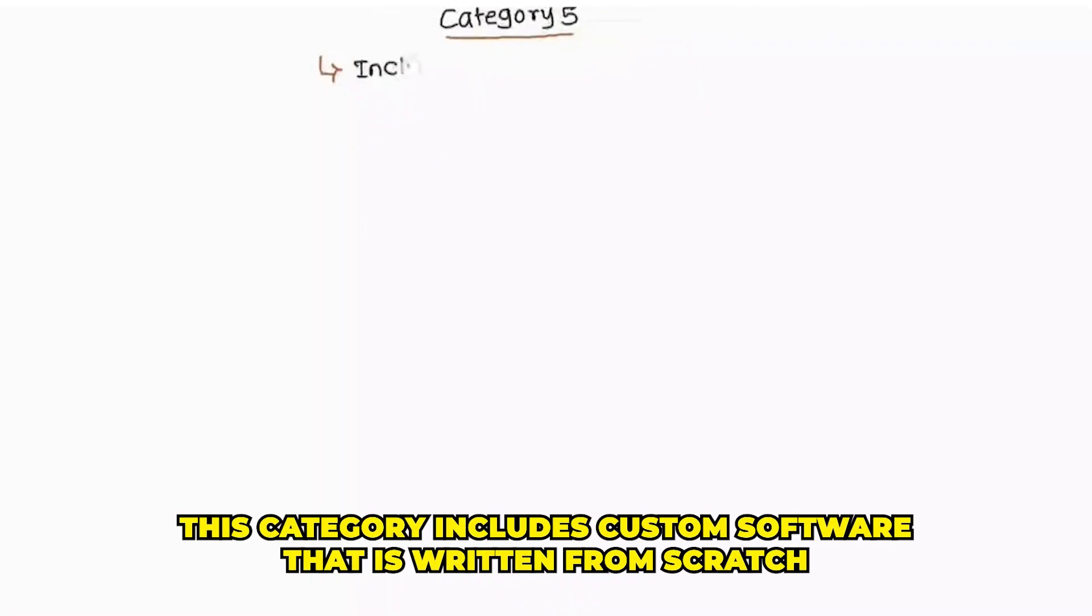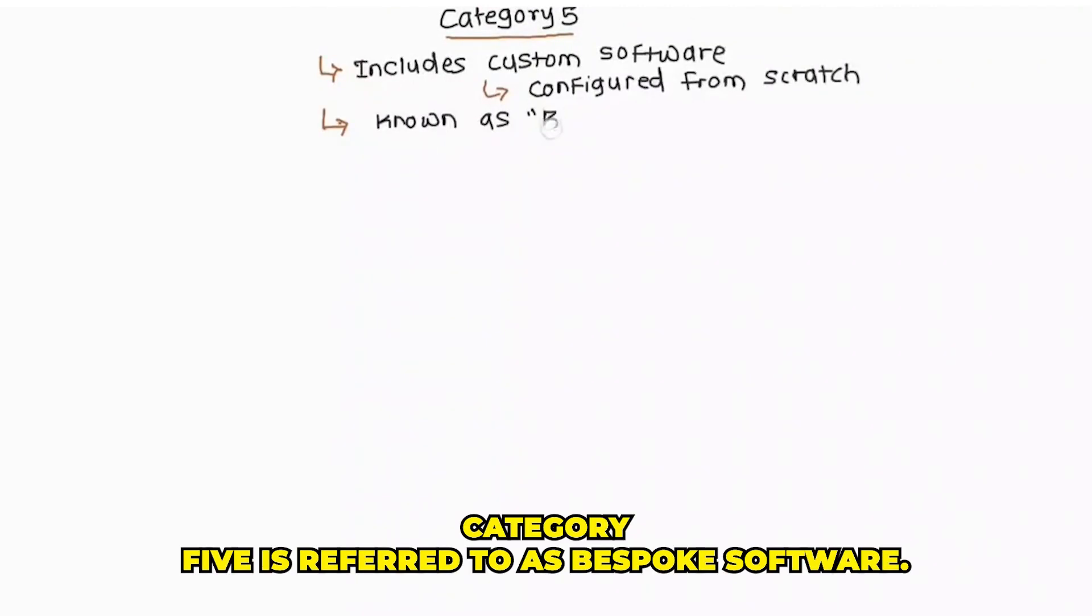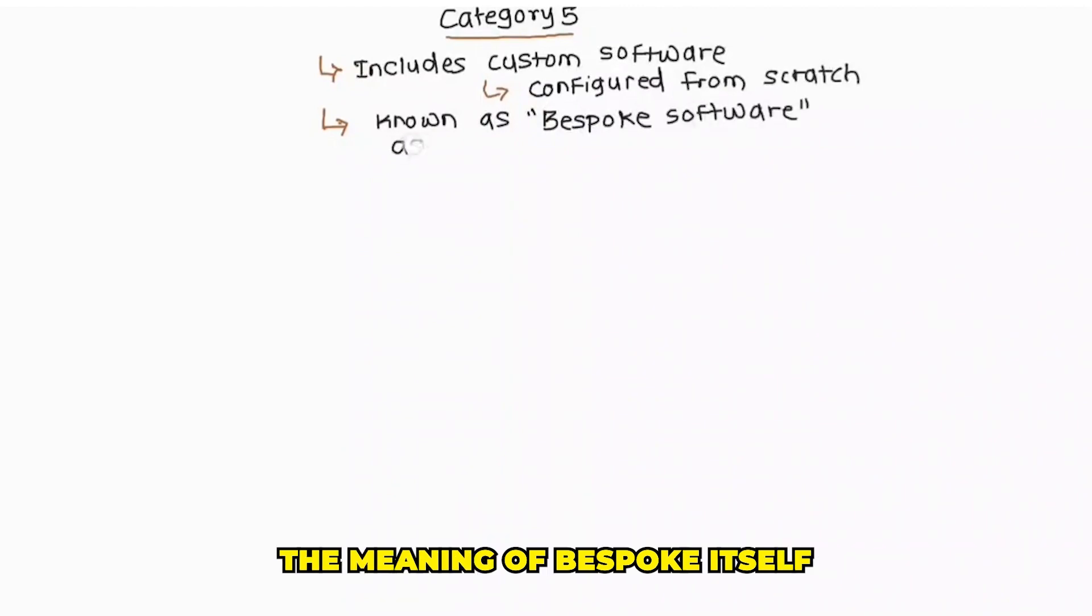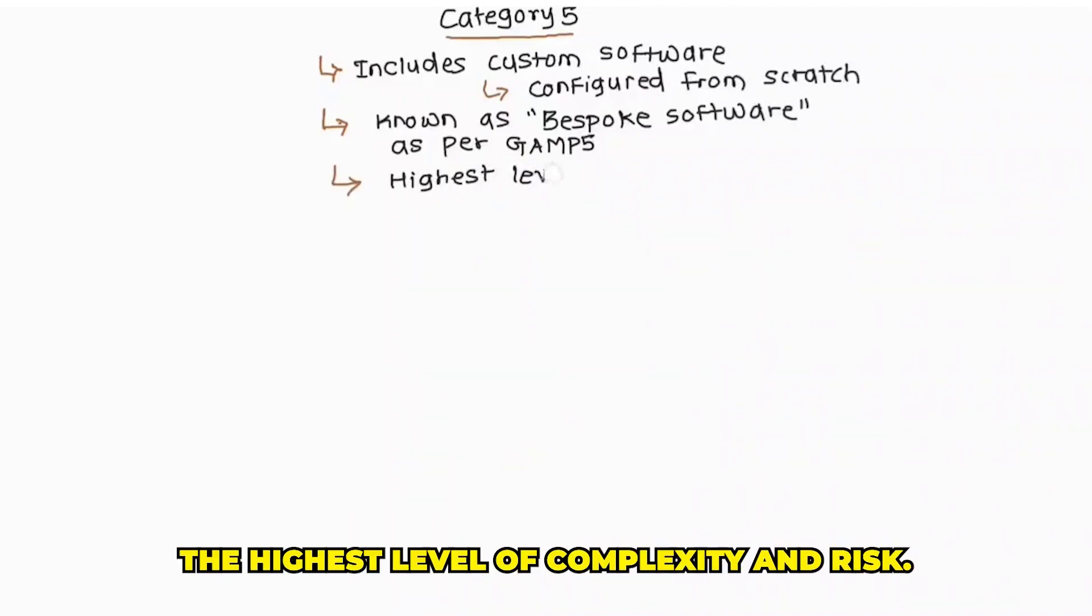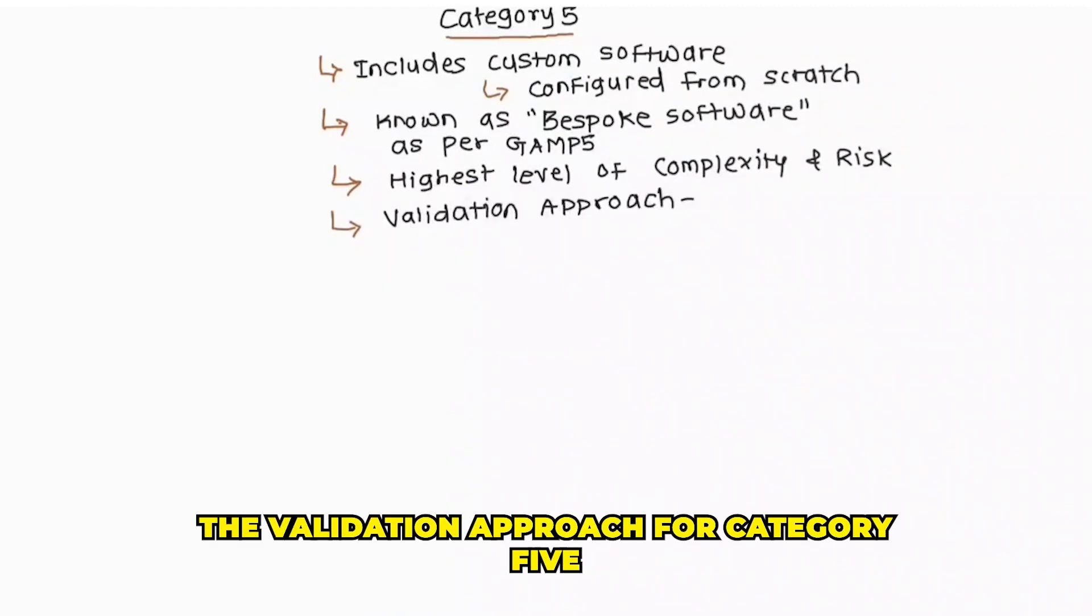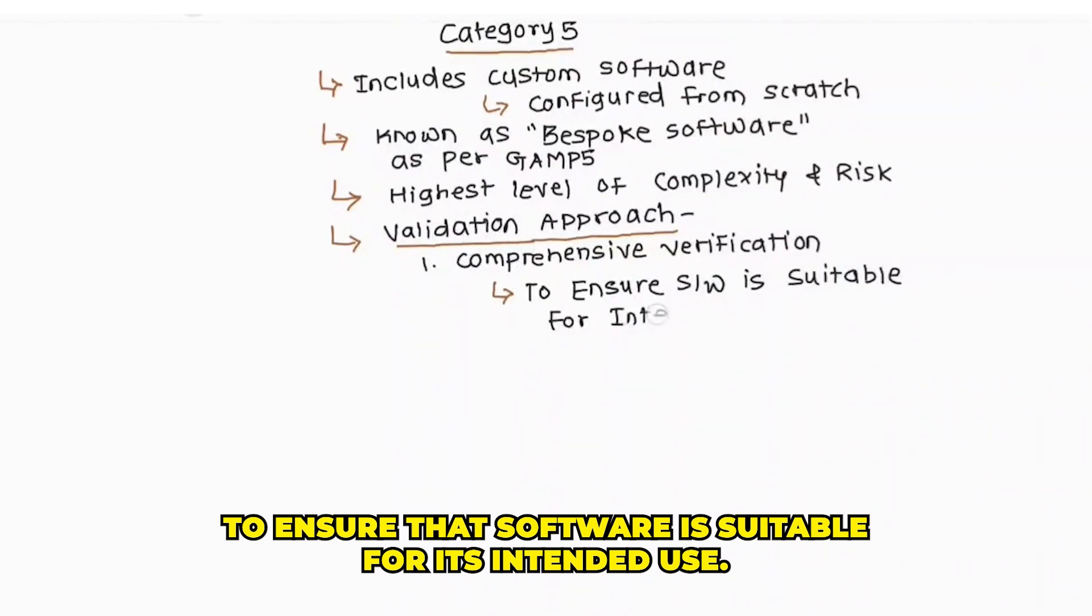Category 5. This category includes custom software that is written from scratch to fulfill specific business needs. In GAMP 5, category 5 is referred to as bespoke software. The meaning of bespoke itself is made for a particular user or customer. Due to its customized nature, bespoke software falls into category 5, which signifies the highest level of complexity and risk. The validation approach for category 5 software involves comprehensive verification activities and documentation to ensure that software is suitable for its intended use.